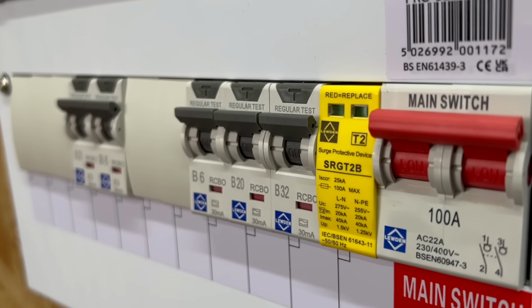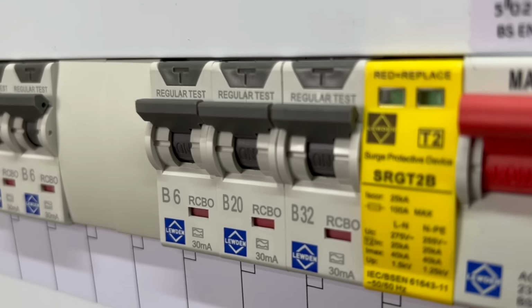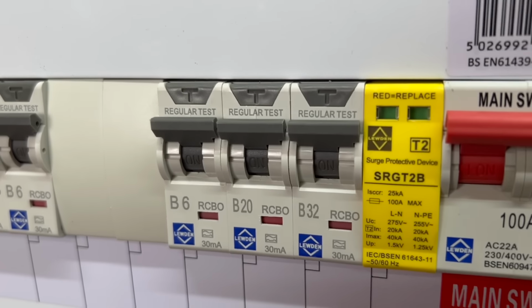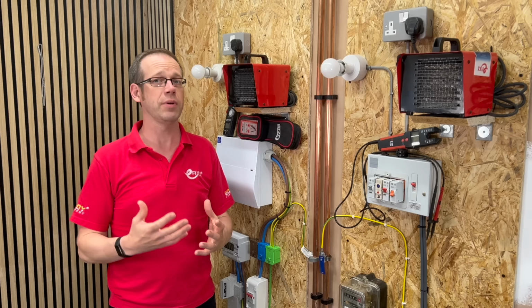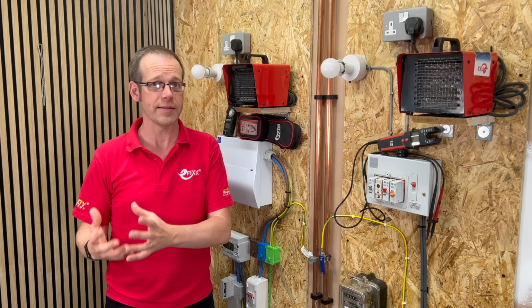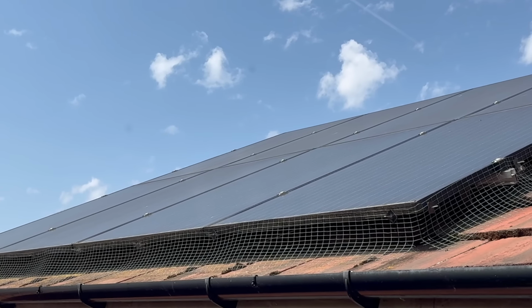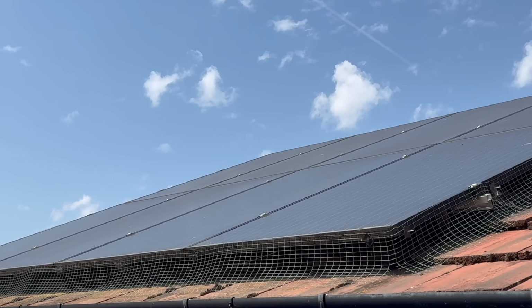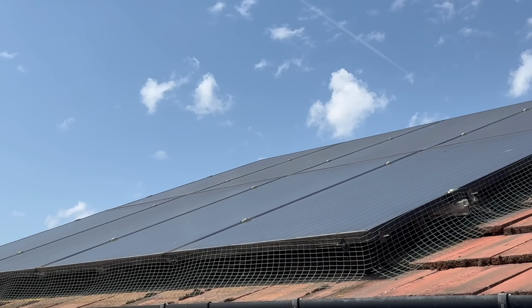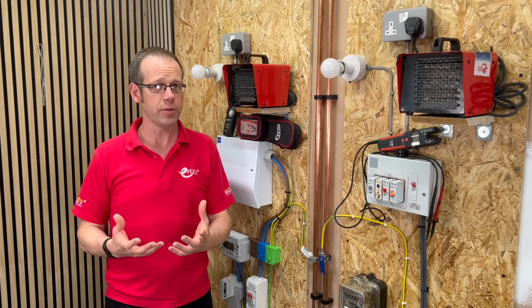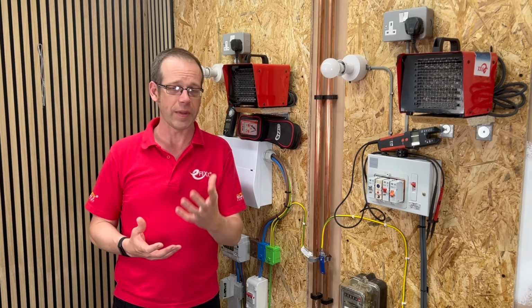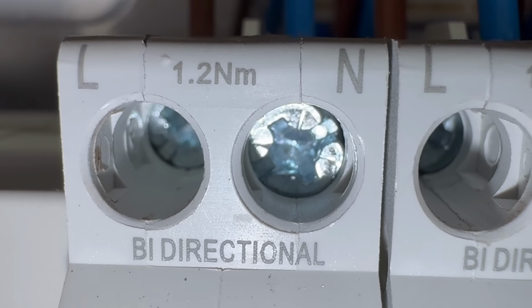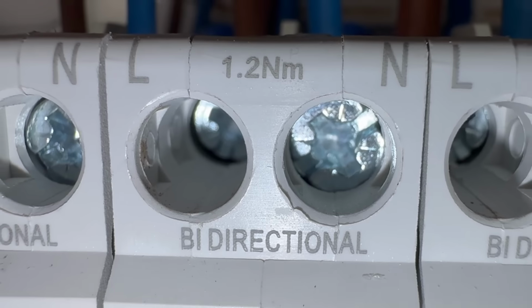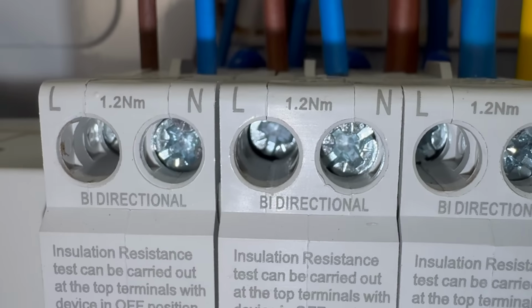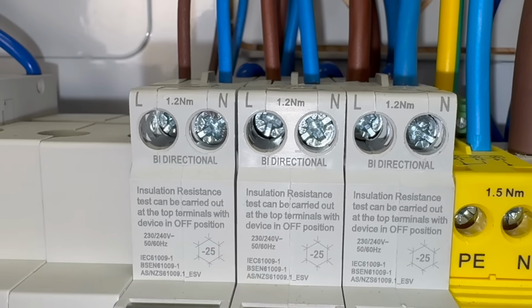Lewden are now producing these bidirectional RCDs. They're critical in modern installations because they allow for the fact that we no longer just transfer energy into an electrical installation, we also transfer it out the other way because of the rise of the photovoltaic panel. There's been a lot of confusion around whether RCDs need to be bidirectional, especially with solar PV systems. In setups where solar panels feed an inverter, then a battery, and finally a consumer unit, RCD protection is required, especially when cables are buried shallowly in walls.